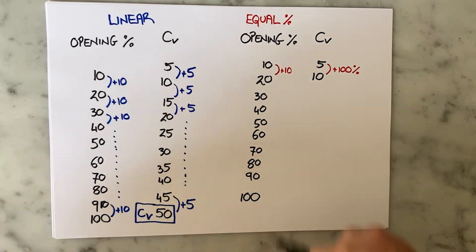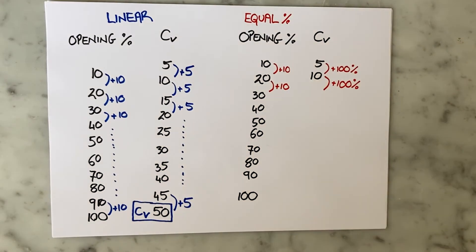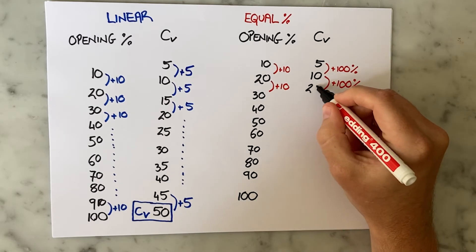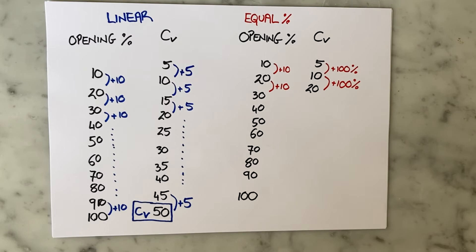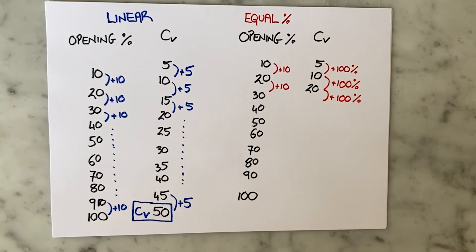In other words, I added an extra 100% of the CV for 10% opening. If I open to 30% I need to add another 100% of the CV, which means at 30% the CV goes up to 20. At 40% opening the CV goes up another 100%, this time to 40.